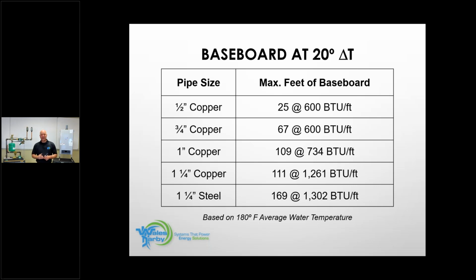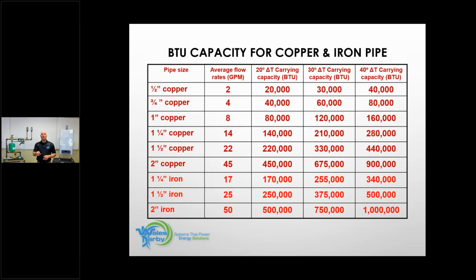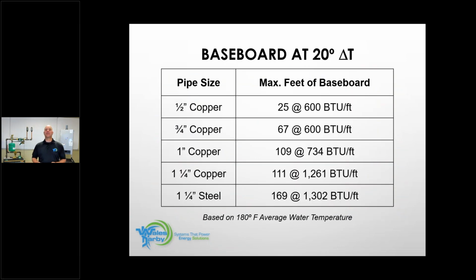So the most common size pipe we see for baseboard heating is 3/4 inch. 3/4 supplies right here. That goes out to a 3/4 baseboard heat circuit. We can have 67 feet of a 600 BTU per foot piece of baseboard heat emitter hooked to that 3/4 pipe. If we did 67 times 600, I believe it's going to be 40,200 BTU, and a 3/4 pipe, which you will see in the next slide, has the ability to carry comfortably 40,000 BTU. So that would be properly sized, right?